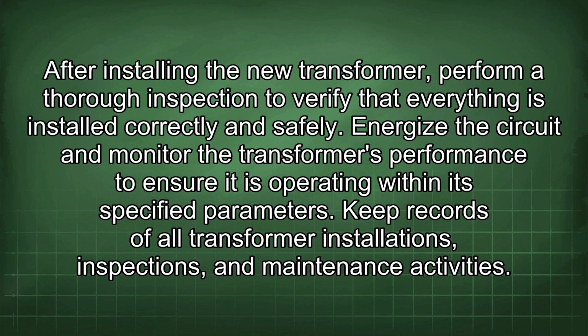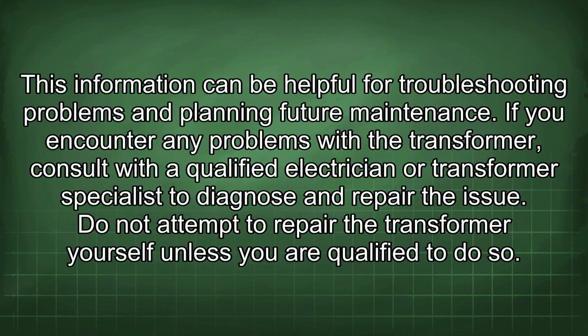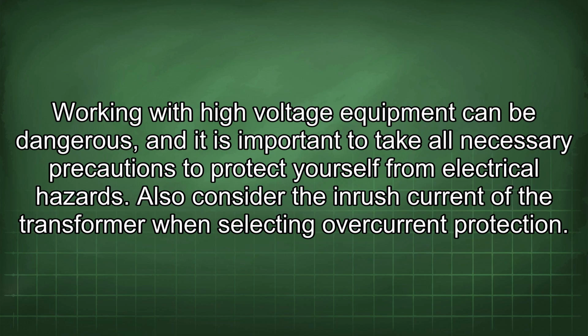Keep records of all transformer installations, inspections, and maintenance activities. This information can be helpful for troubleshooting problems and planning future maintenance. If you encounter any problems with the transformer, consult with a qualified electrician or transformer specialist to diagnose and repair the issue. Do not attempt to repair the transformer yourself unless you are qualified to do so.